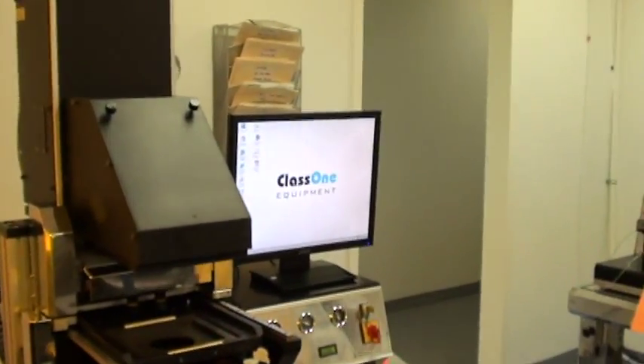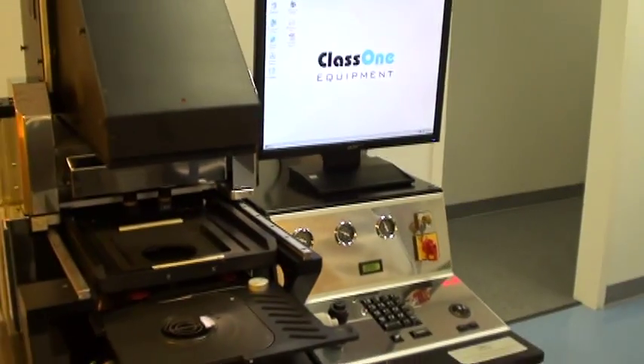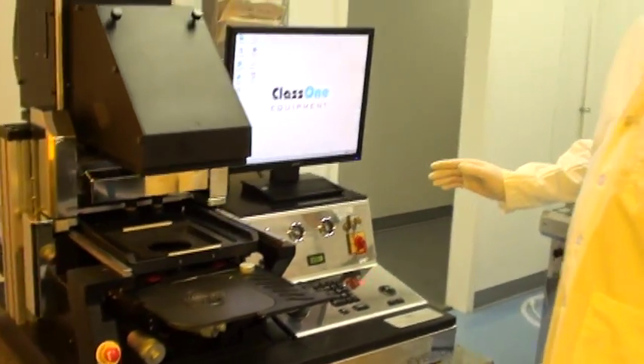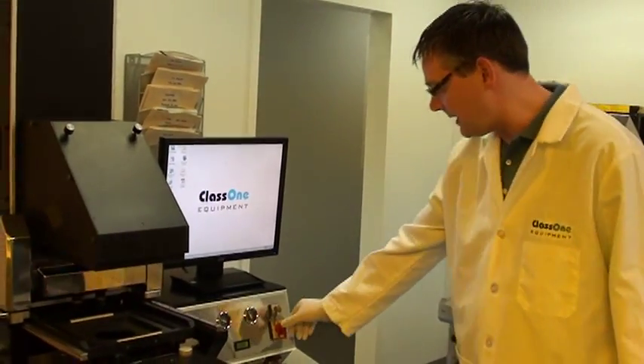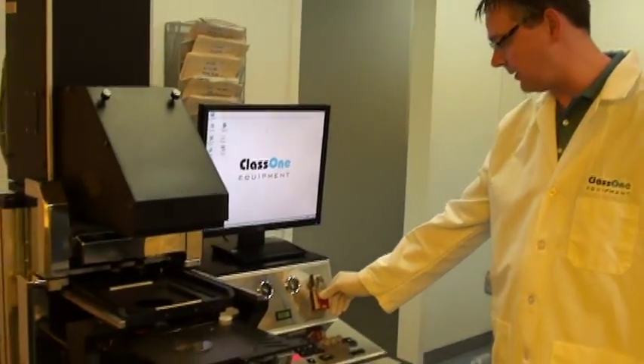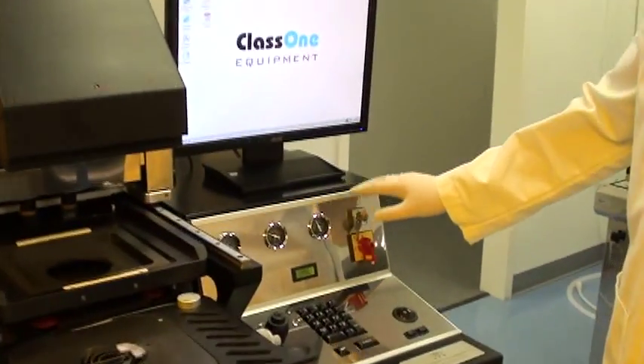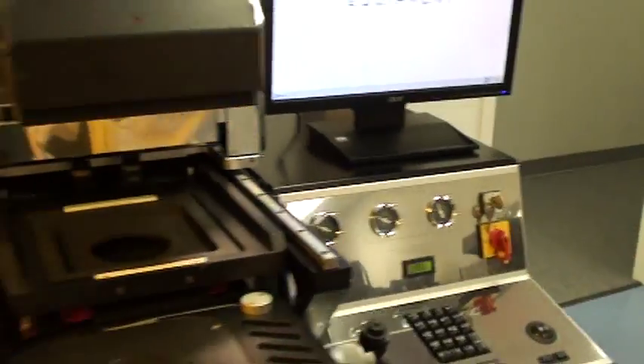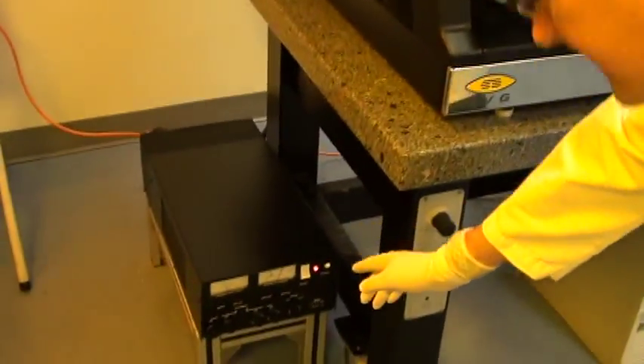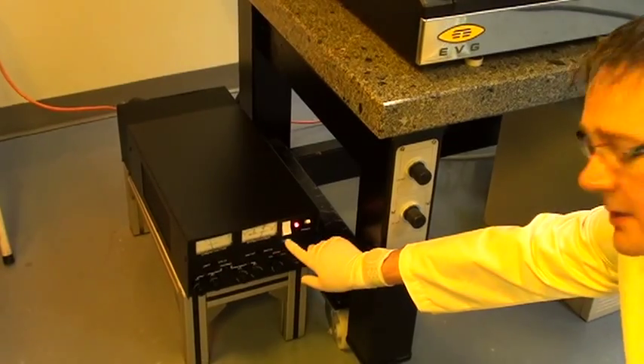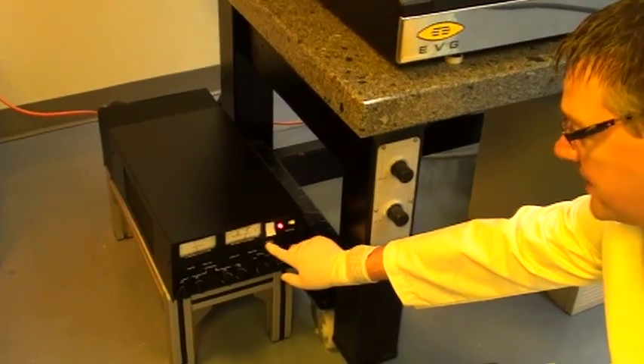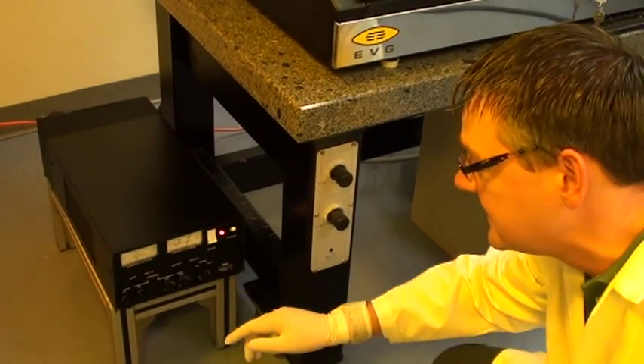So here is the system as you can see we have it powered up. When you start the system you use the main isolator to put the power on leaving the control panel off. Then you power on the lamp house power supply here with the power on, holding the start button down for between three to five seconds. That starts the lamp.